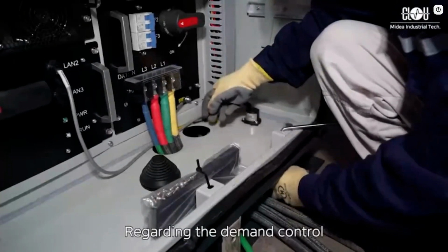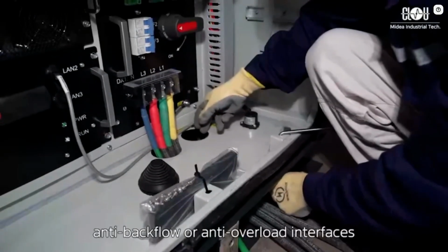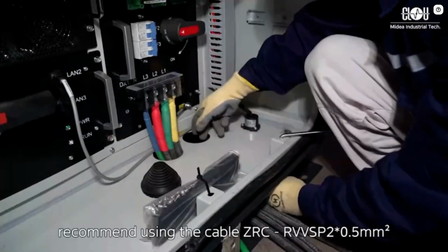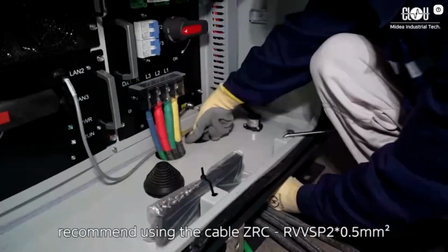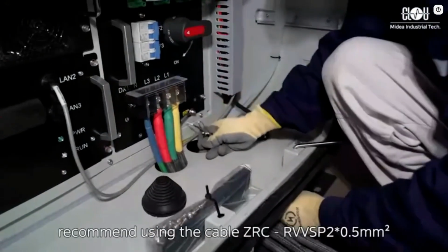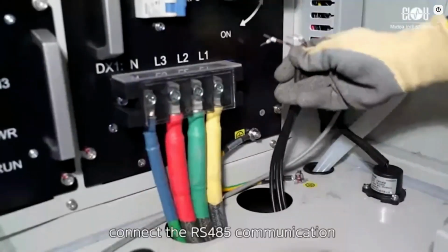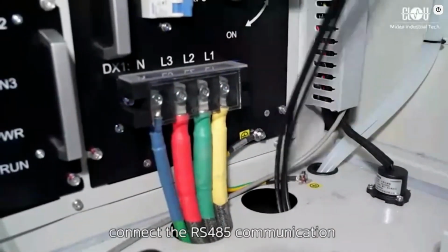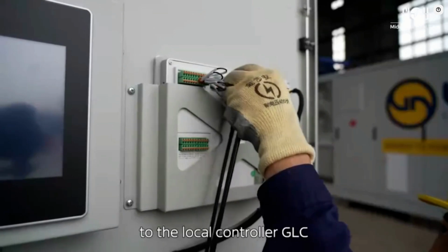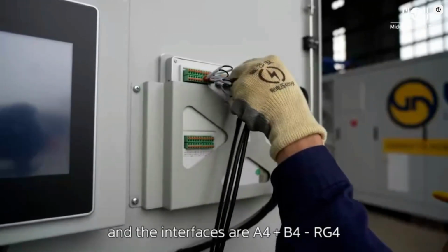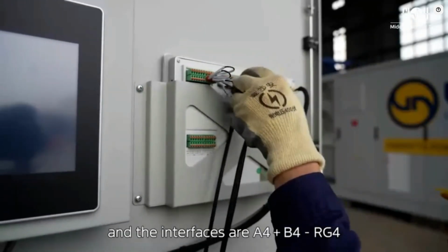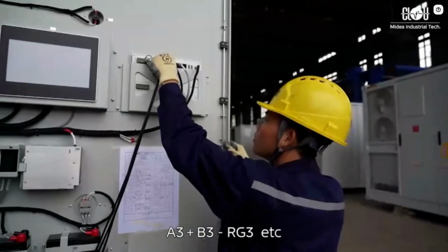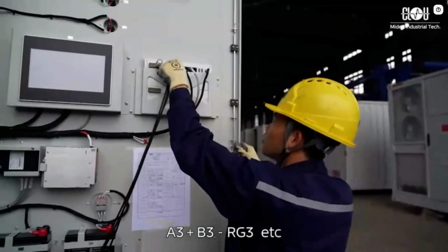Regarding the demand control, anti-backflow or anti-overload interfaces, we recommend using the cable ZRC RVV SP 2x0.5 square millimeters. Connect the RS485 communication to the local controller GLC, and the interfaces are A4+B4-RG4, A3+B3-RG3, etc.